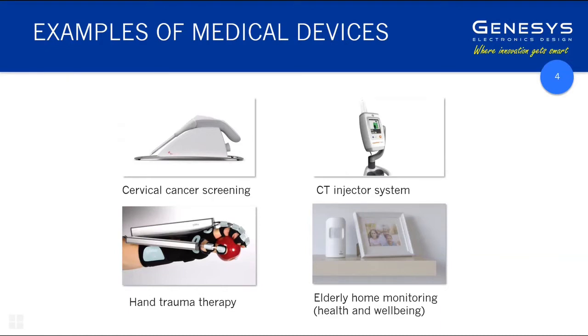So my first question is, do all medical devices require design controls? The short answer is yes, by definition. If it's a medical device, it needs to be put on the market by a medical device manufacturer in accordance with the requirements of ISO 13485, the quality system standard, and that standard prescribes what we call design controls. It's quite interesting what that term means, and we'll talk about that in a minute.